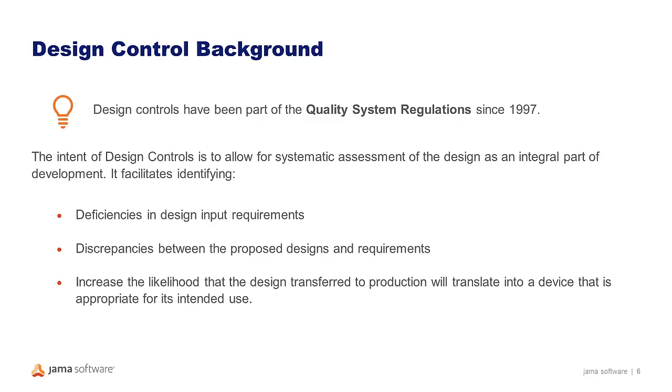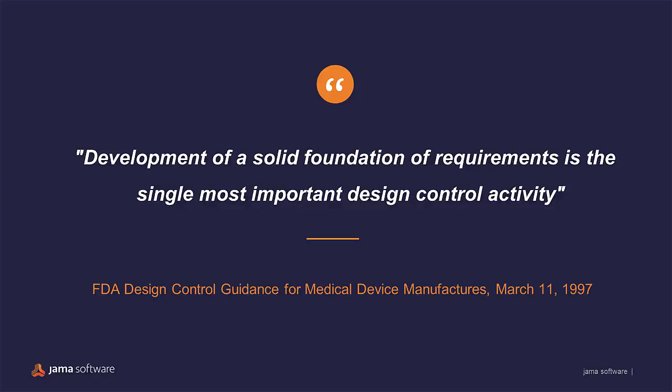And they did this in relation to having a lot of issues in the field with medical devices. So they thought design controls would improve the quality of the medical devices that were being approved. In the FDA design control guidance, they state that developing a solid foundation of requirements is the single most important design control activity. So that kind of tells you how important FDA thinks design control requirements management is.